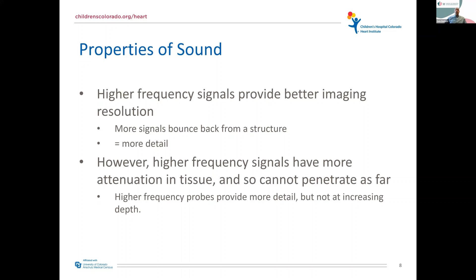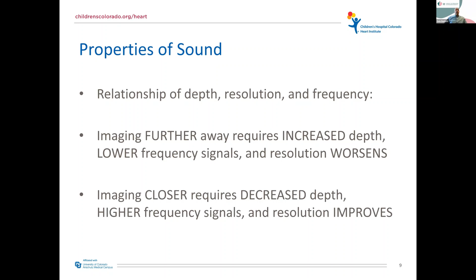But higher frequency actually attenuates in tissue, so it doesn't travel as far. And so that's why you need to use lower frequencies when you're imaging deeper structures. So there's a relationship of depth, resolution, and frequency here that I think is worth highlighting. If you're going to image things that are further away, you have an increased depth that's going to take longer time again. You're going to want to use lower frequency because it's further away, but you're also simultaneously getting lower resolution. Conversely, if you're imaging things that are closer at decreased depth, you can use higher frequency signals and you have improved resolution. So this is one of the common reasons why, when you look at an infant's echocardiogram, everything looks really great. And then you look at your 25-year-old ACHD patient and you can't see much.